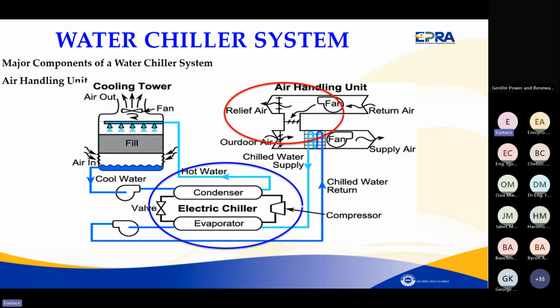Because in most cases, and we have found this in the audits we get, when somebody is going to audit a chiller system or an air conditioning system, they learn very fast to establish the coefficient of performance or the energy efficiency ratio of that system. Let me tell you, you cannot establish that, because if you want to establish it as it is written in the nameplate of that system, it's not possible, because when the energy efficiency ratio or the COP was being established, it was established on controlled conditions.